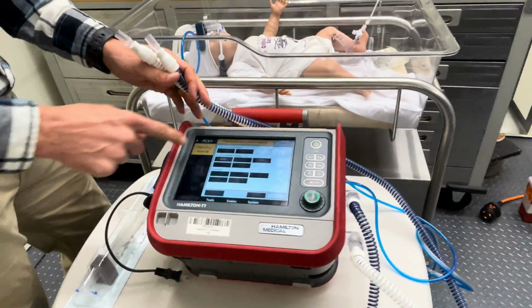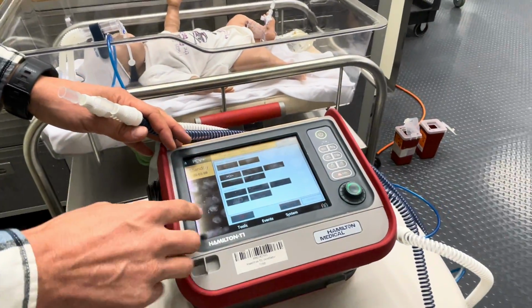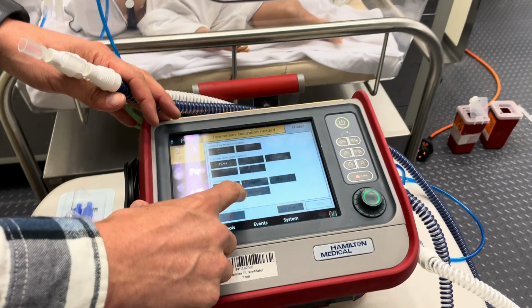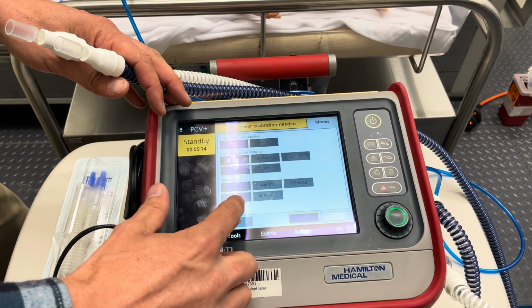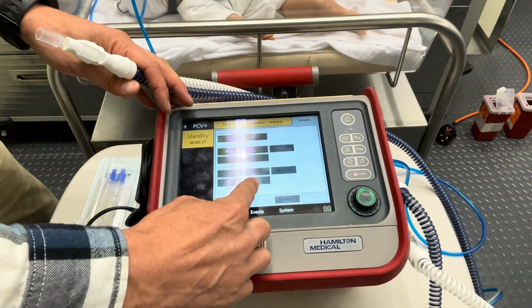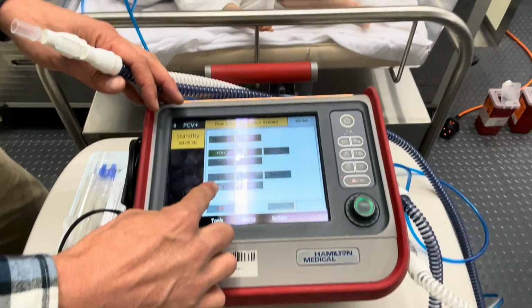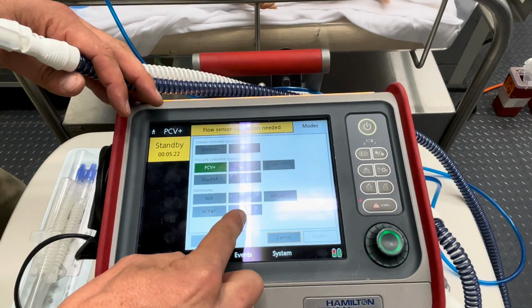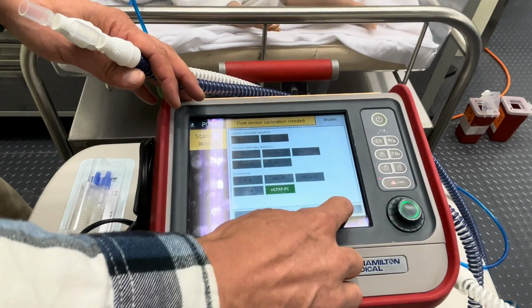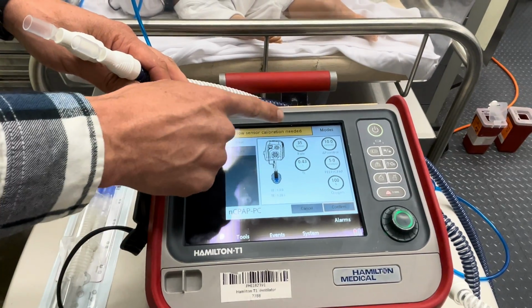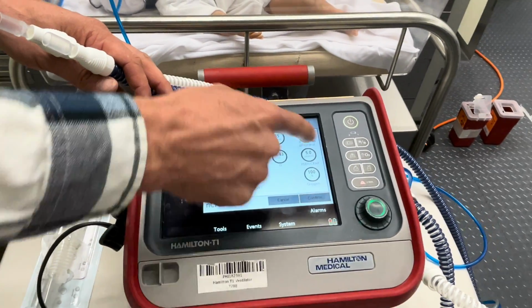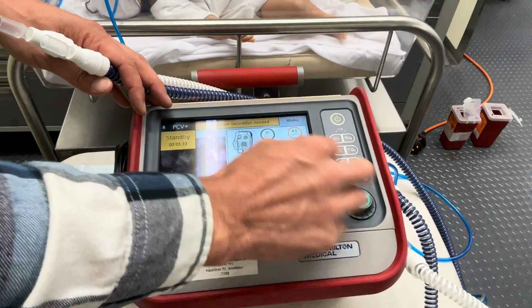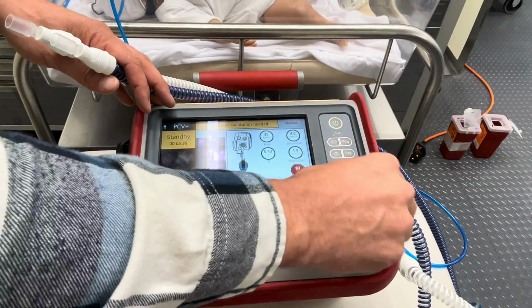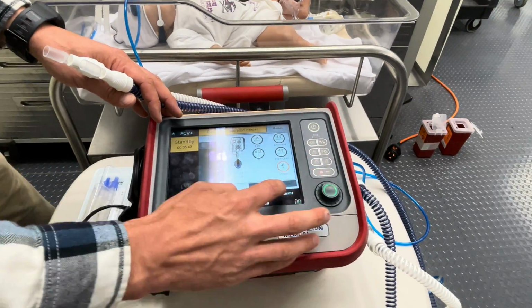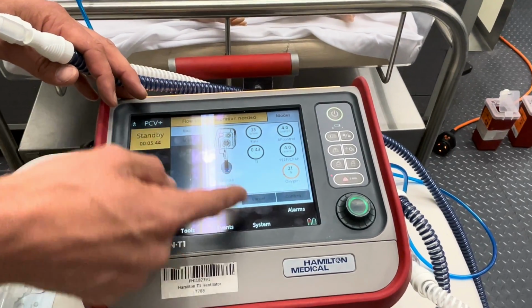So you're going to click on modes, and there are only two modes that you can use with this setup: neonatal nasal CPAP and neonatal nasal CPAP PC. You can think of this as CPAP and this as BiPAP. So this is one pressure all the time. This is an inspiratory and an expiratory pressure with a rate. We'll do that one because there's a little more to it. So once we click confirm, we'll choose the respiratory rate and our I time. In this case, we'll just set this to say 4/4 and 21% oxygen. So those are our settings. That should give us 8/4 for the BiPAP.